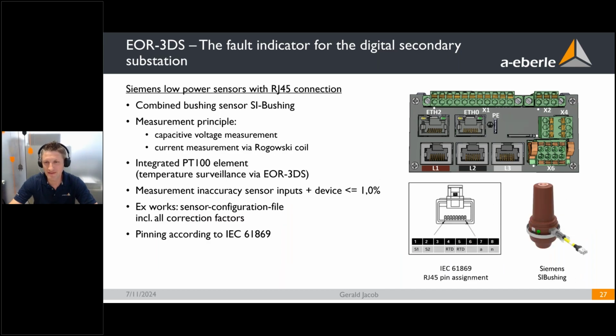And shortly compared to the Siemens SI bushing, this one is newer. This one is only available regarding the new standard 61869. And as you can see here, the pins for the current are already on the first and the second pin. And in addition, we have here a PT100 internally integrated in the Siemens SI bushing, and the device is able to measure on all 3 phases the internal temperature of the bushing, which is quite helpful, for example, for the asset management.